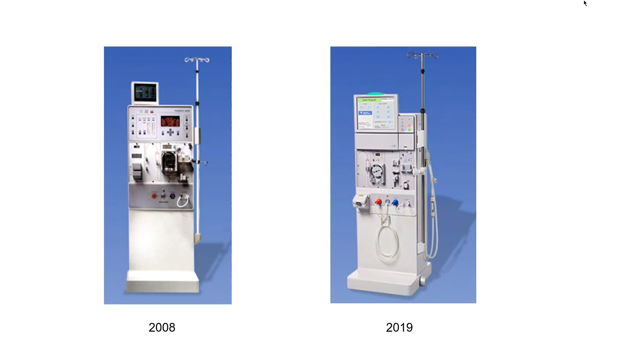Patients' electrolytes and pH at critical levels, and still the setting on the conductivity alarm can be manipulated? Yes, but to a safe degree, up to 1 millisiemens, so it's supposed to be 0.5 up and below. But if you put all of that on the low end, for example, or the high end, that can potentially be an issue.